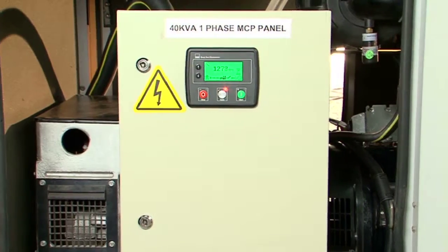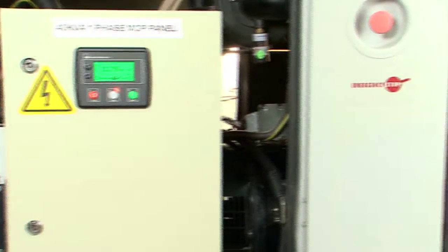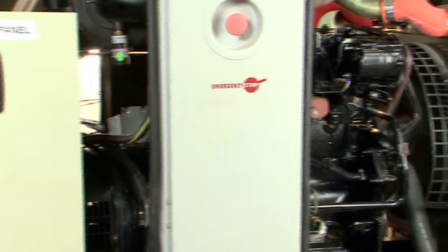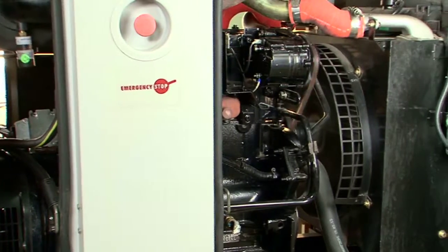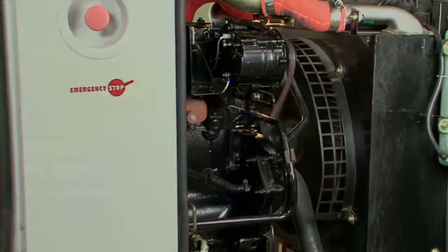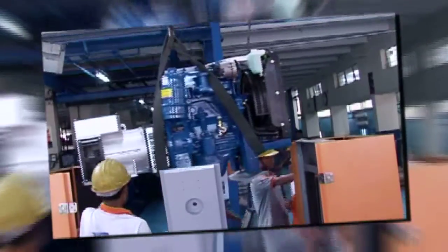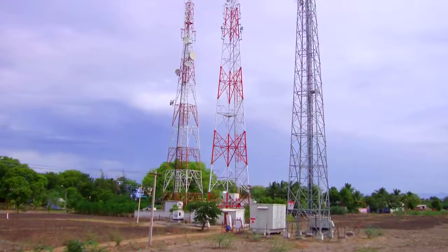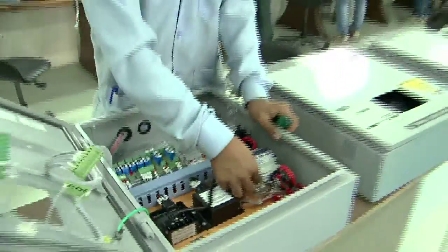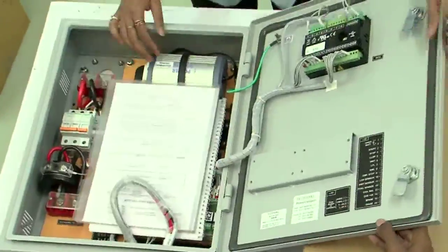Now, let's take a look at the important characteristics of the new variable speed genset technology. And let's look at the features one by one. Compatibility with new and existing gensets. The first important feature is that this variable speed technology is available for new gensets as well as existing gensets in the field. For existing gensets in the field, this technology is available as a special retrofit kit.